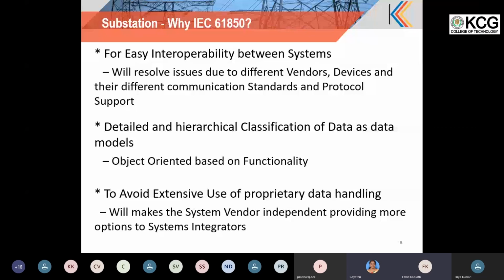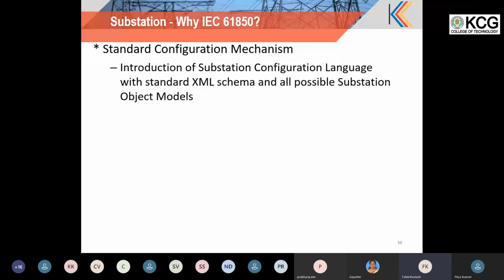To avoid extensive use of proprietary data is one of the key aspects. So we need to avoid all vendor dependent data from the system. It needs to be completely vendor independent. Other protocols were not focusing on representing a standard configuration mechanism, that is, what my communication aspects are, what the logical nodes, functionality and data are. These are represented using an XML schema and possible substation objects. We have defined as part of the 61850 standard a configuration mechanism using an XML schema in XML language. This configuration is defined. This is one of the key aspects.